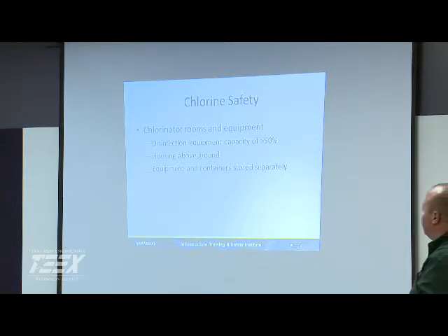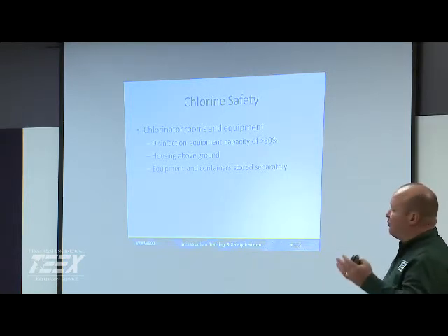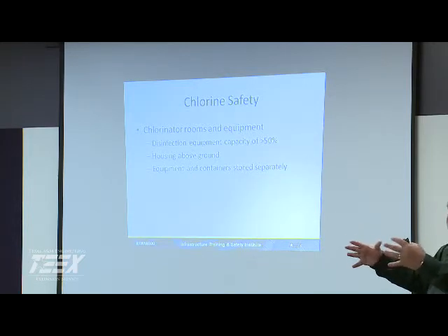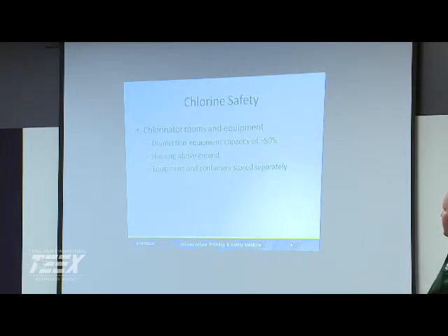Because chlorine is heavier than air, we definitely want our stuff up above ground. We don't want it down in low-lying areas. We want our containers and our rotameters and all, if we can, to be separate. Some real small buildings, you can't. If you can, that's obviously preferred. You've got to bring air in, force the air from the top, and let it be pushed out the bottom.